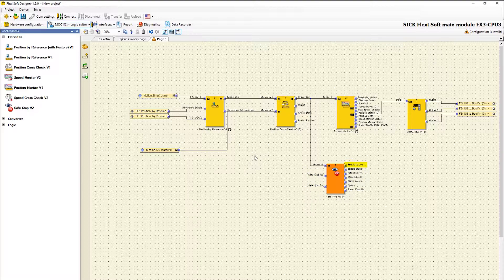The signal Enable Torque is used to switch off the torque of the drive system directly. Enable Brake is used to switch off the power supply to the mechanical brake directly. Amplifier Off triggers the shutdown of the amplifier via the PLC. The torque and the brake of the drive system can be switched off. The output Stop Request triggers the stop ramp of the drive.